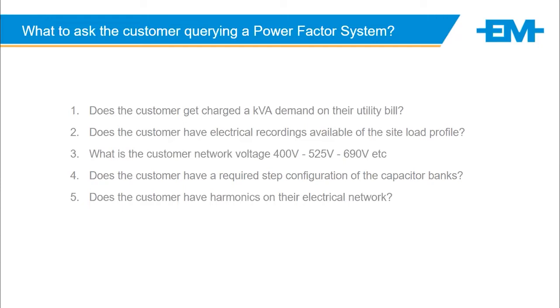A lot of mistakes customers do make: is my network 400? Is it 525? Is it 690? We need to know this. Does the customer already know the step configuration that he needs? Does the customer have harmonics on their network? Most customers would not know this. You will identify this in the site load profile, which you would do with a power analyzer. All right.